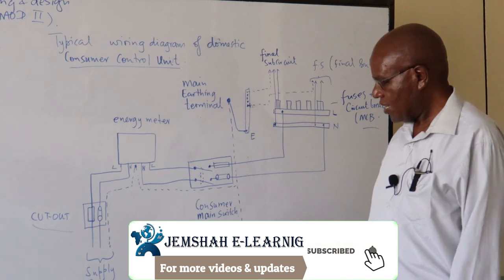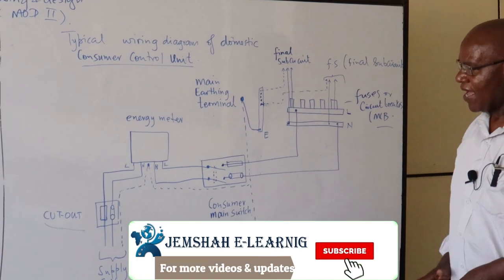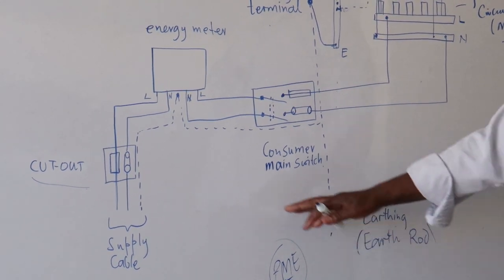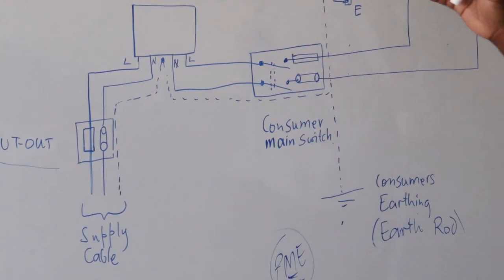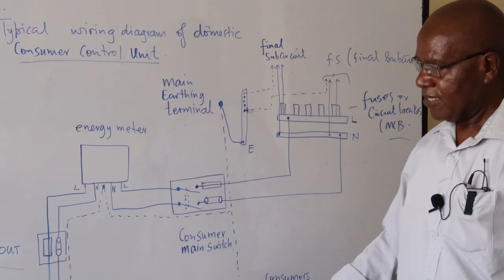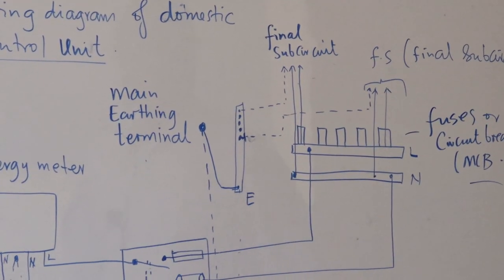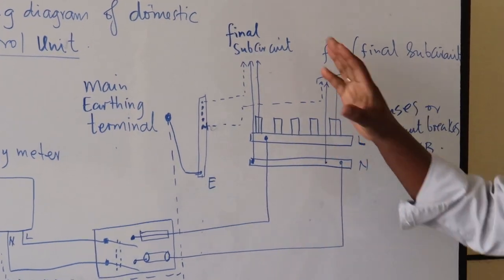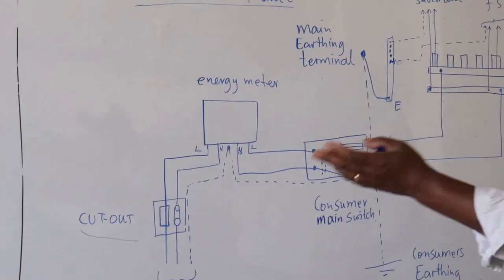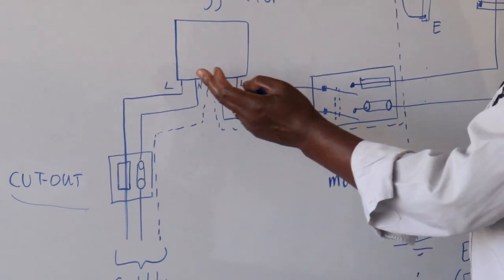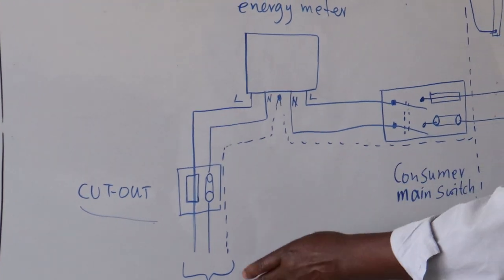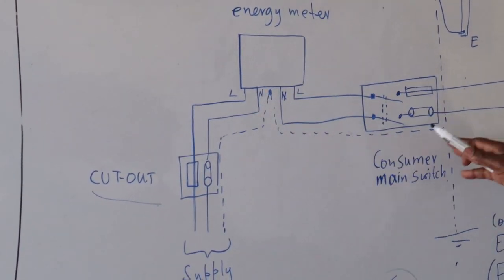Sometimes you may be forced to take in additional rodding or go for some other earthing arrangements. The PME is used in areas where the earth loop impedance is a problem. In Nairobi nowadays, in most installations they tend to go for this arrangement whereby the power supply earthing and the consumer's earthing all join together at one point. The only thing I want to talk about is the energy meter — the live is in the extreme left and comes out on the extreme right, the neutrals are the ones in between, and you may have an earthing terminal where you connect the incoming cable and also take it into the building.